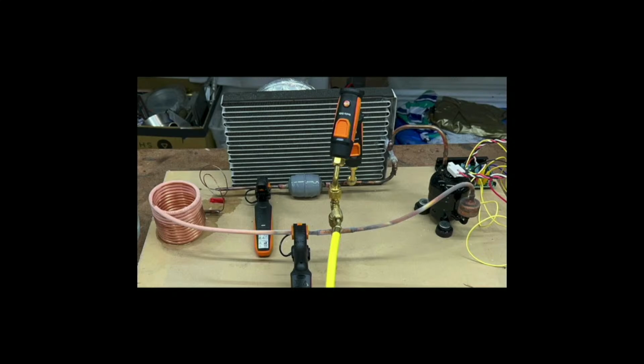You also see two pressure sensors and two temperature sensors. All you're doing is making sure the high pressure side is high enough pressure and the low pressure side is low enough pressure, using lookup tables based on the refrigerant you're using. If you have too little refrigerant, the high pressure side won't be high enough. If you have too much, the low pressure side would be too high. This is something that I think can be easily automated with a $50 Arduino shield if we wanted to. And there you have it - it's a working refrigeration loop.